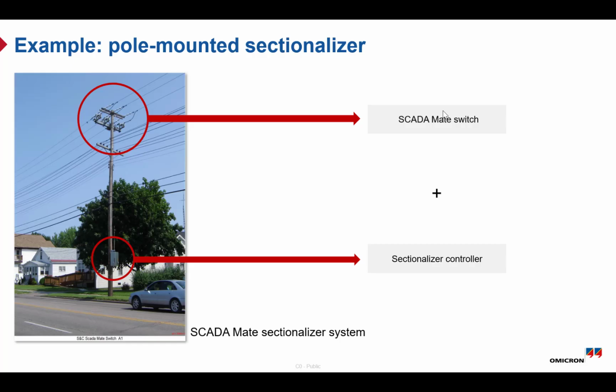In terms of components, we mainly have the switch on top and the controller unit below. Some setups may also include communication and a VT for power supply, but overall it's a simpler system compared to a recloser. And one of the main advantages is low cost, as sectionalizers are typically more economical since they don't include a full circuit breaker.